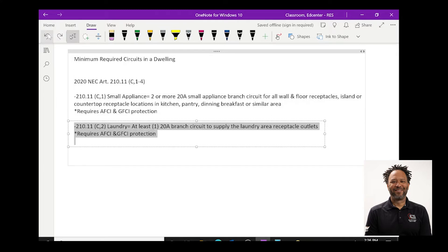The next required circuit that is listed in 210.11c2 is your laundry circuit and this states that at least one 20 amp branch circuit to supply the laundry area or receptacle outlet or receptacle outlets shall be required.